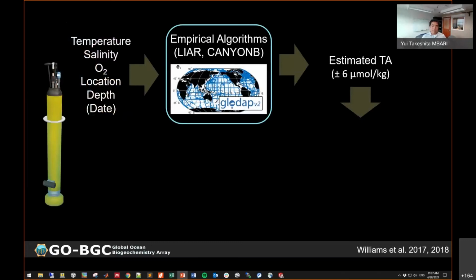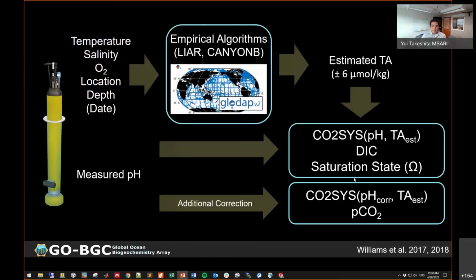Okay, and then using pH, we can calculate derived parameters for the carbonate system as well. We estimate the alkalinity using an empirical algorithm with the same inputs, and the algorithm can estimate alkalinity to about 6 micromole per kilogram. You combine that with the measured pH, and then you can derive parameters such as DIC, saturation state, and PCO2. One thing I want to mention is that we use measured pH directly for DIC and saturation state, but when we calculate PCO2, we apply an additional correction. This comes from the fact that pH and PCO2 aren't exactly internally consistent, so there's some lack of knowledge in the CO2 system. And yeah, you can see the talks for more details on that.